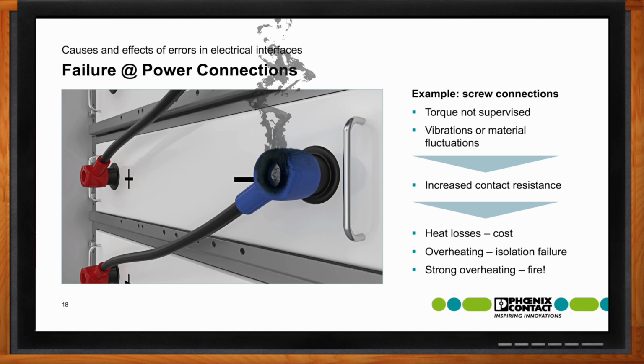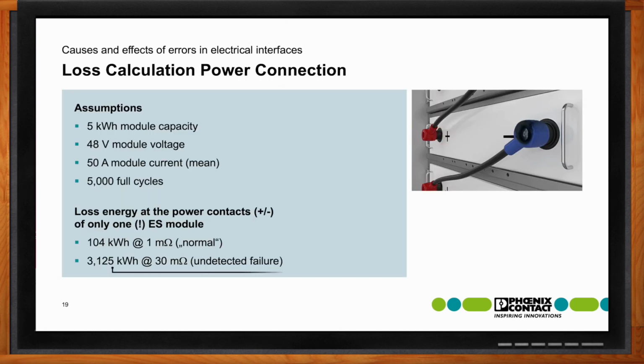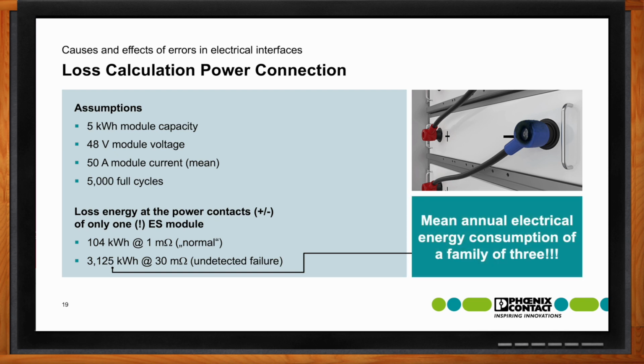I have done a kind of loss calculation with certain assumptions shown on this slide, with a standard battery module of 5 kilowatt hours of capacity, 48 volt module voltage, 50 amps of mean module current. I calculated this for 5,000 full cycles, which more or less relates to the lifetime of such a battery module. If we look at only the two battery poles shown in this picture on the right-hand side, they always have a kind of transition resistance, normally around 1 milliohm, giving energy losses of around 100 kilowatt hours over the whole lifetime, only at this one single battery module—and there are a lot of them inside an energy storage system.